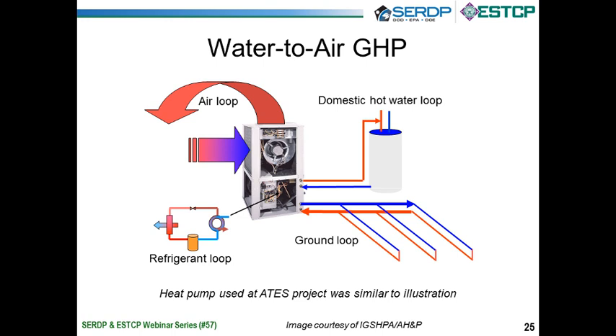This is an illustration of a water source heat pump like you might find at Fort Benning or in my home. It is very analogous to a traditional heat pump, except that the compressor is on board. So in the illustration there, you'll see a coil with the blue arrow is the air, in this case in the heating mode. Cold air hits the coil. It gets pulled into that centrifugal fan you see. Warm air blows out. If you reverse the flow, then you can actually have the air coming in and being chilled and blowing out. Down in the bottom section there, in the lower left, you see the refrigerant loop.